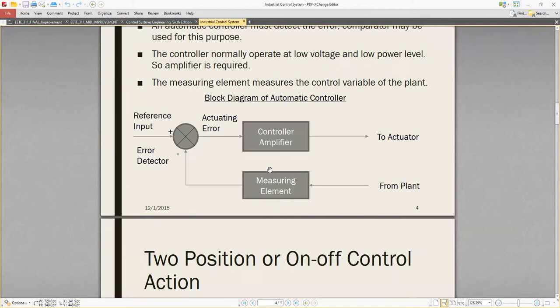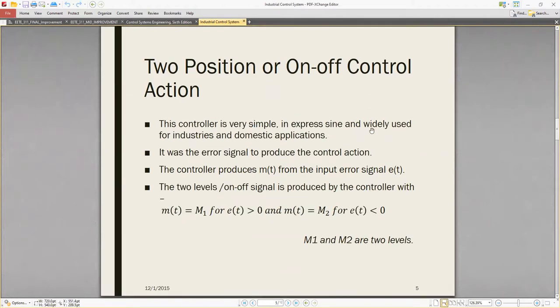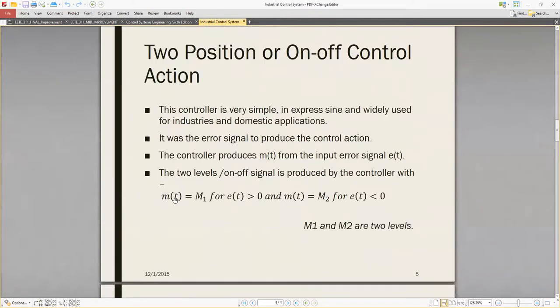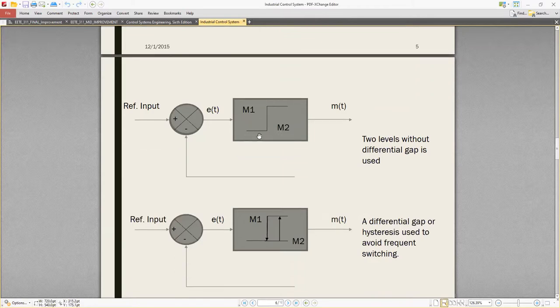The two-position or on-off controller is very simple in design and widely used for industrial and domestic applications. It uses the error signal to produce the control action. The controller produces the output m(t) at two levels: m(t) equals m1 when the error e(t) is greater than zero, and m(t) equals m2 when the error is less than zero. These are the two levels — m1 is the higher level, m2 is the lower level — and two levels without a differential gap are used.